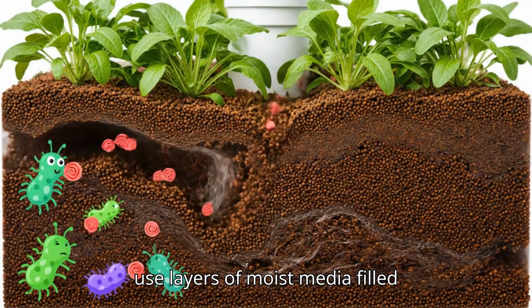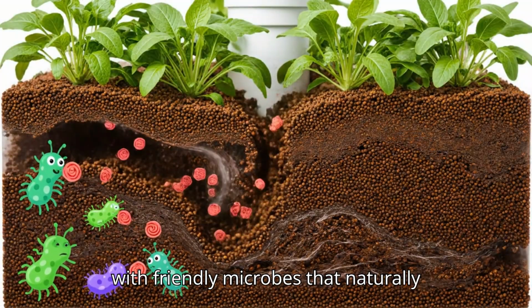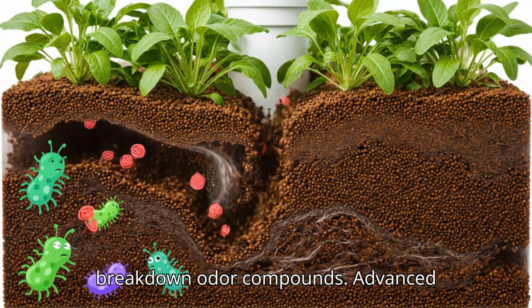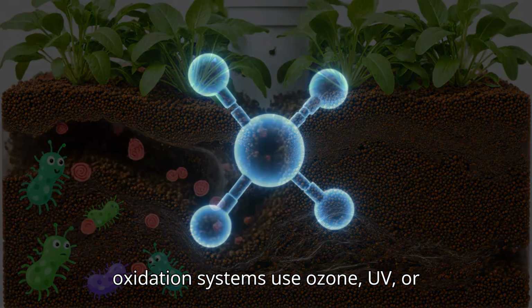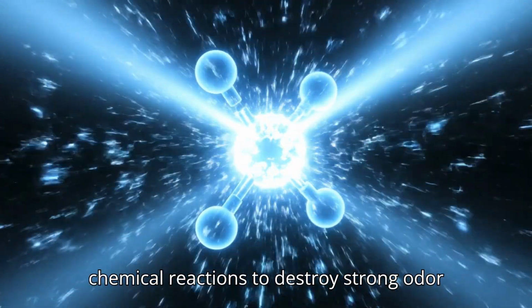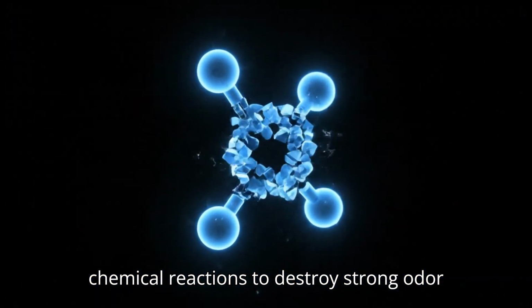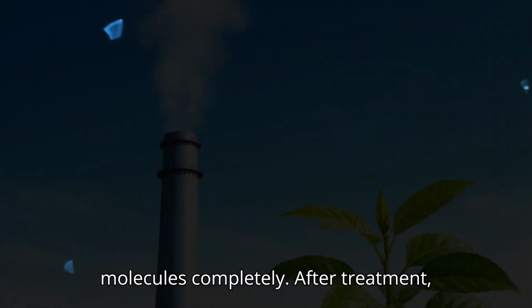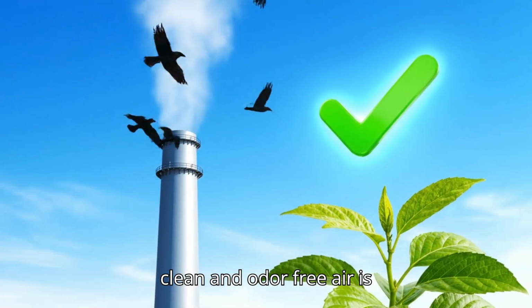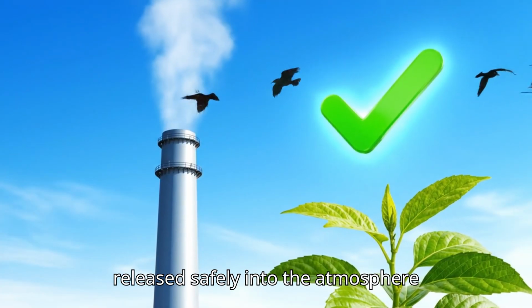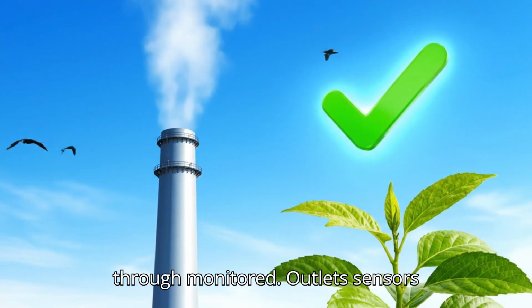Biofilters use layers of moist media filled with friendly microbes that naturally break down odor compounds. Advanced oxidation systems use ozone, UV, or chemical reactions to destroy strong odor molecules completely. After treatment, clean and odor-free air is released safely into the atmosphere through monitored outlets.